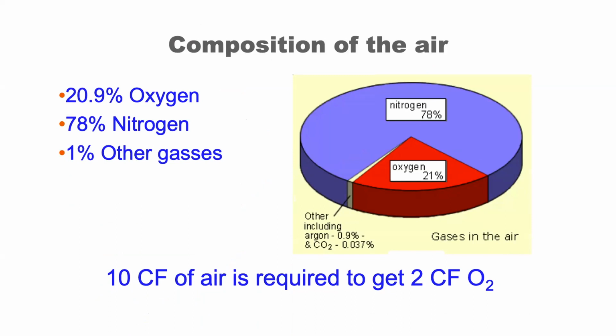So like we hinted at there, air is mostly nitrogen, 78% nitrogen, about 20.9% oxygen, and about 1% other gases. And because of that, you need a lot of air to get the right amount of oxygen. So if you need 2 cubic feet, for example, of oxygen for combustion, you'll need to pull in 10 cubic feet of air because air is only approximately 1/5 oxygen. So this gives you an idea. There's other things going on or moving through the combustion system beyond just oxygen.